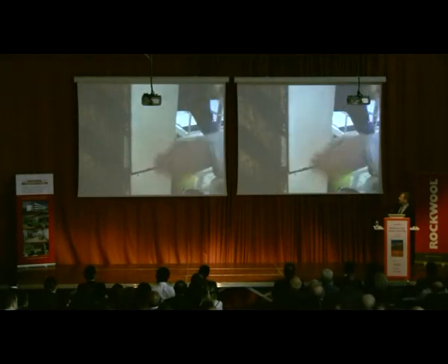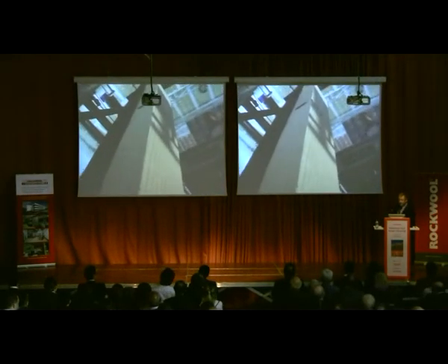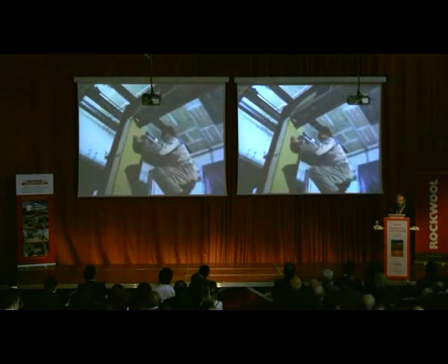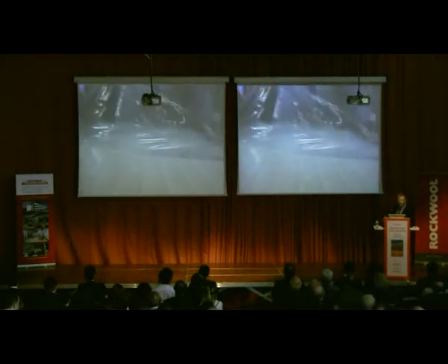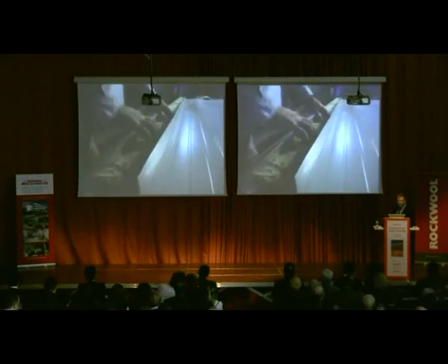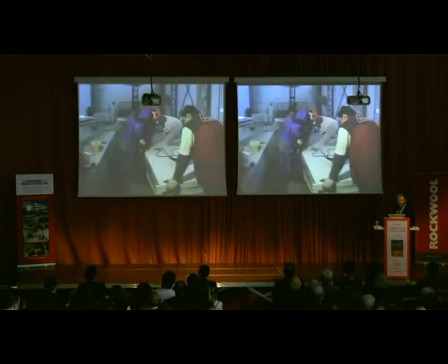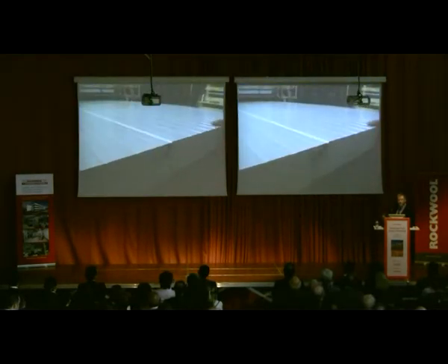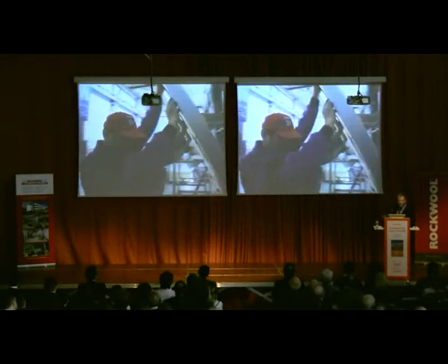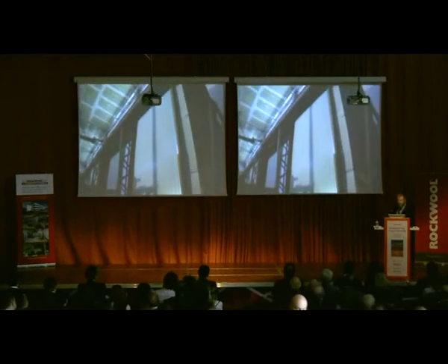And you will see how these products are installed in practice. The goal should be to simulate the real life installation as much as possible. You can see stone wool is used in fire testing laboratories quite commonly to seal any kind of gaps, to prevent direct attack of flames on the insulation core. Of course, the installation should be made the same way like it is done in practice.